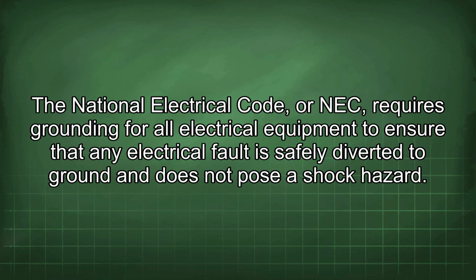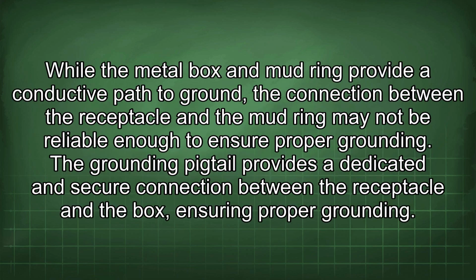The National Electrical Code, or NEC, requires grounding for all electrical equipment to ensure that any electrical fault is safely diverted to ground and does not pose a shock hazard. While the metal box and mud ring provide a conductive path to ground, the connection between the receptacle and the mud ring may not be reliable enough to ensure proper grounding. The grounding pigtail provides a dedicated and secure connection between the receptacle and the box, ensuring proper grounding.